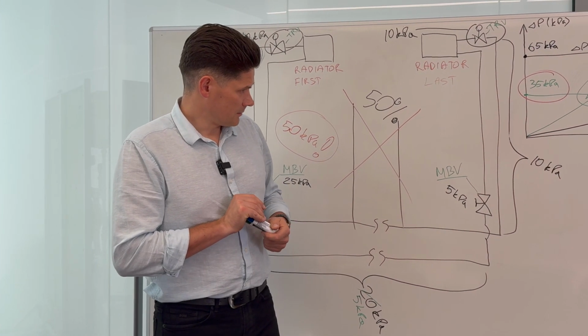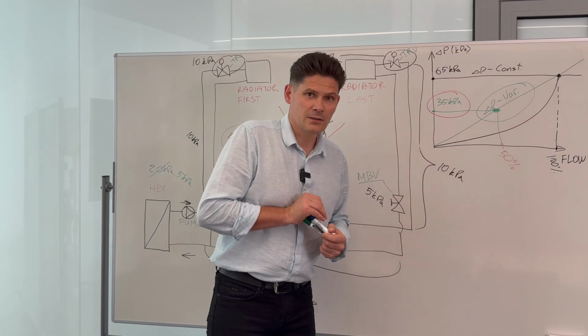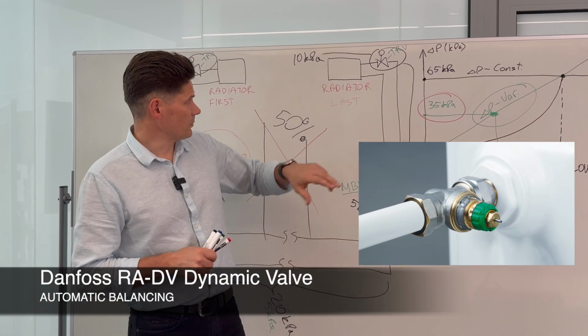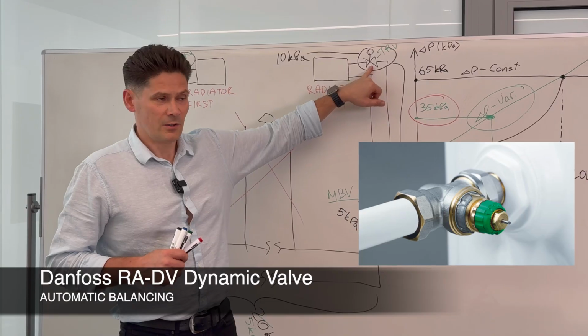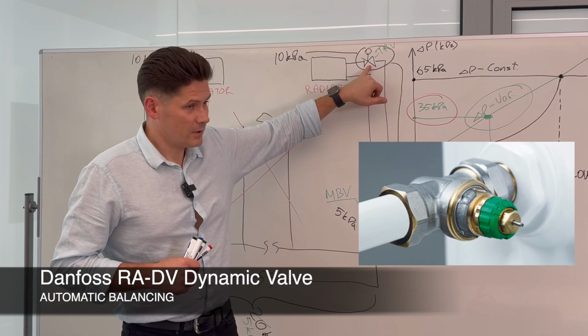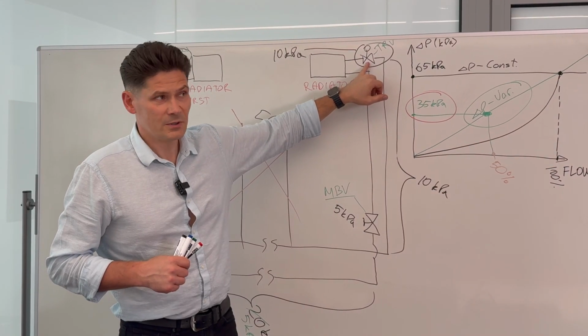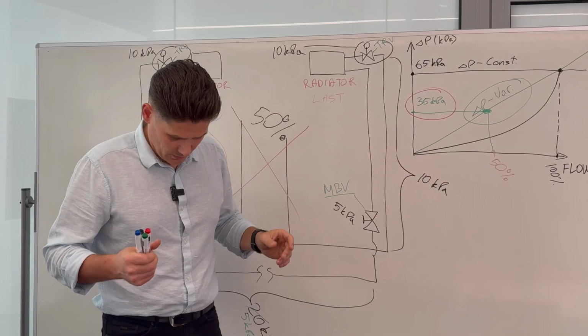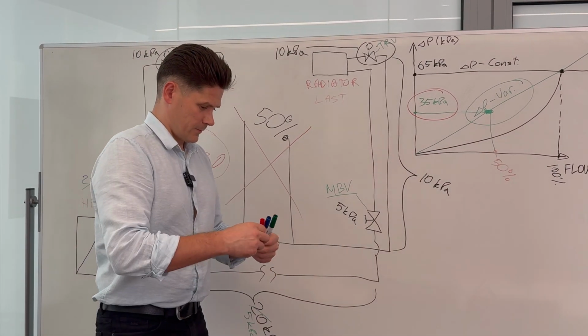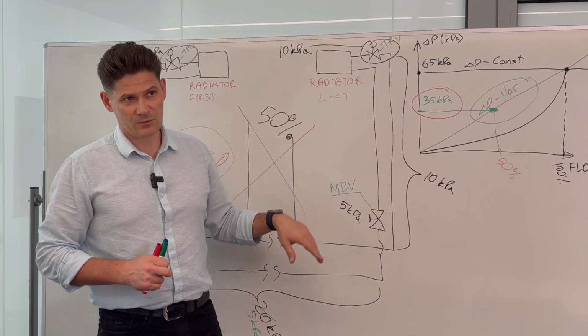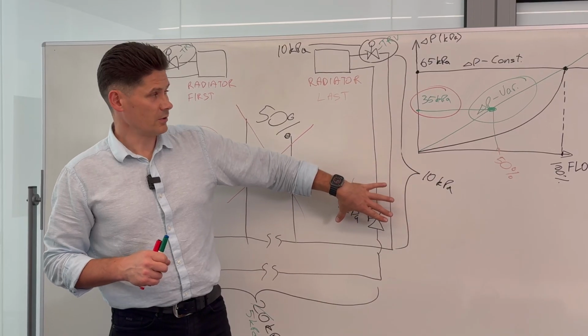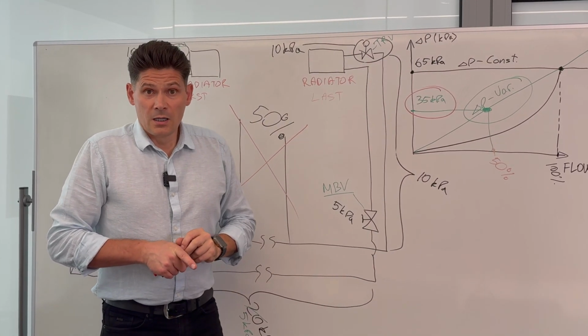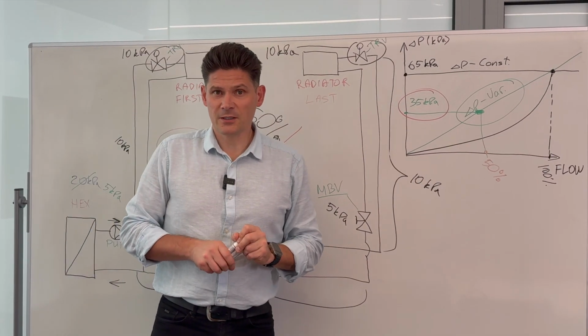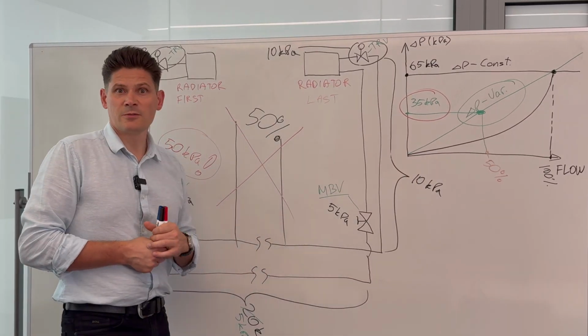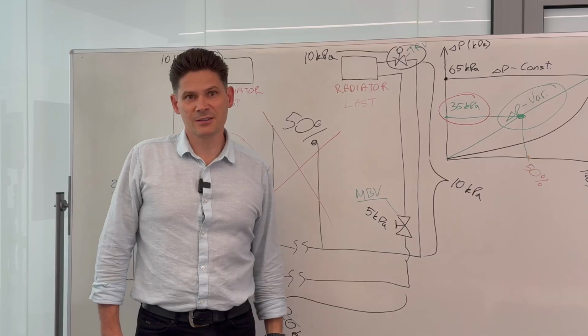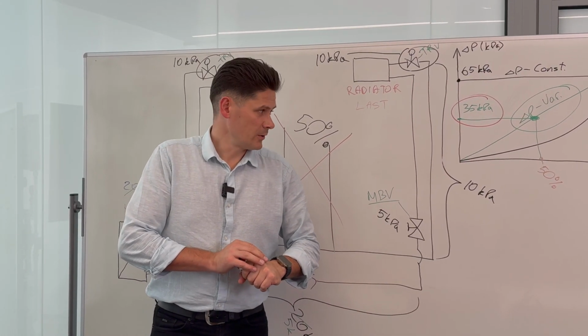Okay, here we should use delta P controllers, pressure controllers for risers, or for smaller systems there are small dynamic valves, RADV. It is called RADV. Dynamic radiator valves, where we can put a dynamic radiator valve here, which is pressure independent and needs no balancing valves, but it is limited to 60 kilopascals, so it can be used for smaller systems, or with delta P controllers it can also be used for bigger systems. Or we need to use delta P controllers for risers, and then we can use RADVs. Okay, so this is my answer why manual balancing valves are not suitable for balancing in modern systems with modern circulation pumps controlled with frequency converters.